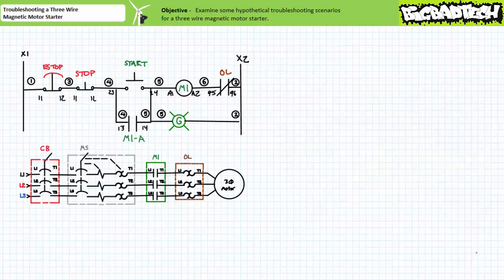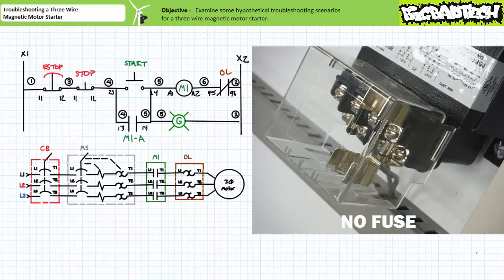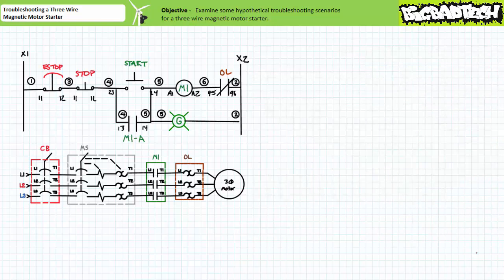Let's examine the nature of the holding circuit and discuss its implications. Let's say the control transformer has a blown fuse and cannot properly energize the M1 contactor coil. In this case, primary power to the motor is still available. It's just the pilot ladder logic will not function. A technician can, however, manually override the malfunctioning pilot level ladder logic and manually force the contactor closed.